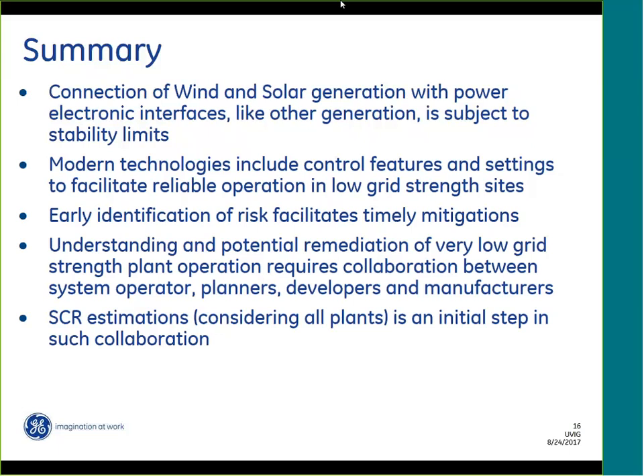Yeah, that's becoming more and more frequent. The experience is that those can be made to work. There are risks of interactions, but in principle they can be made to work. The experience that may be relevant in North America is that we've looked at projects where a significant amount of wind gets connected to the rectifier end of HVDC, even the standard LCC HVDC, which is typically used for bulk power. We've seen that all the features developed to get wind turbines to operate stably in weak systems are very helpful when connecting a large amount of wind to a rectifier end of an HVDC.